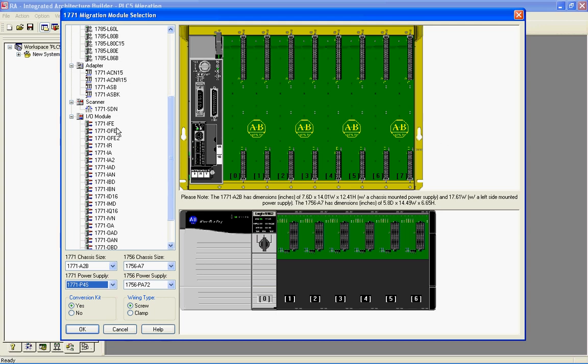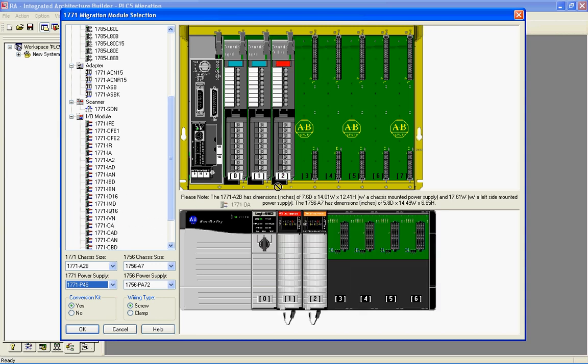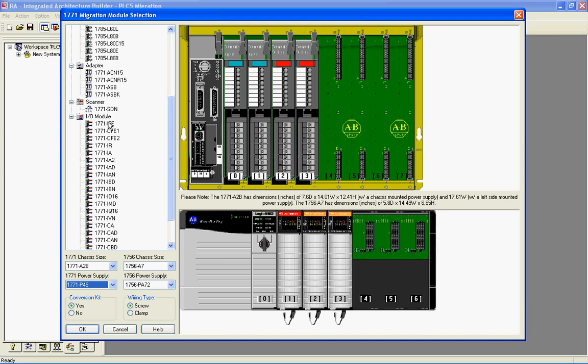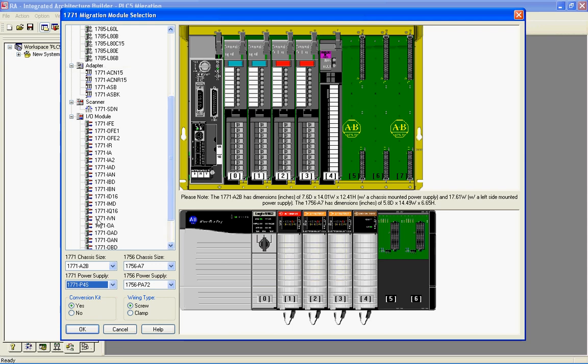I'm going to populate this PLC-5 chassis with a few I/O modules — a 1771-IA, just an AC input. I'll drop a couple of those in. An OA is an AC output module — I'll drop a couple of those in as well. You'll see it prompts me in some cases to pick a variety of options to correctly choose the wiring conversion adapters I need. In this case, it asks if I've got single-ended or differential voltage or current inputs, so I'm just going to pick single-ended voltage mode.